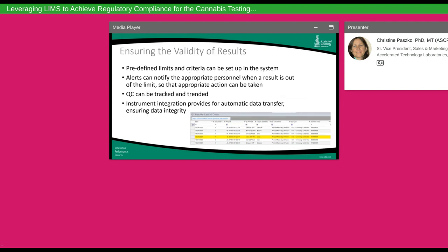Another process requirement is data integrity — ensuring the validity of results generated by your laboratory. Instrument integration provides automatic transfer of data into the LIMS with no opportunity for transcription errors. The LIMS also allows users to set up specifications or limits for different tests, methods, and matrices, so that if data coming in from an instrument breaks a limit, it automatically displays a color-coded alert to the end user. Those alerts allow the analyst to take appropriate action, including spawning automated emails to a supervisor. QC results can be checked and trended, and if a retest is needed, the sample can be sent back for retesting.